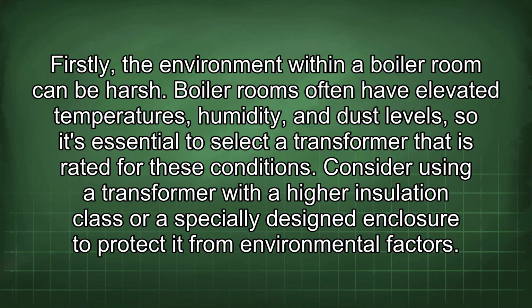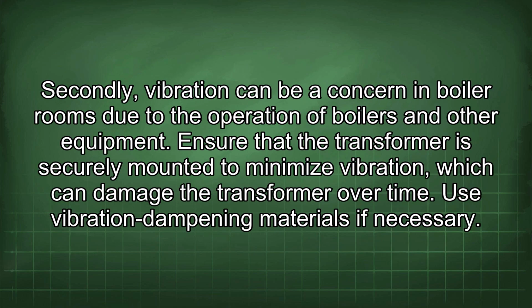Boiler rooms often have elevated temperatures, humidity, and dust levels, so it's essential to select a transformer that is rated for these conditions. Consider using a transformer with a higher insulation class or a specially designed enclosure to protect it from environmental factors. Secondly, vibration can be a concern in boiler rooms due to the operation of boilers and other equipment. Ensure that the transformer is securely mounted to minimize vibration, which can damage the transformer over time. Use vibration dampening materials if necessary.